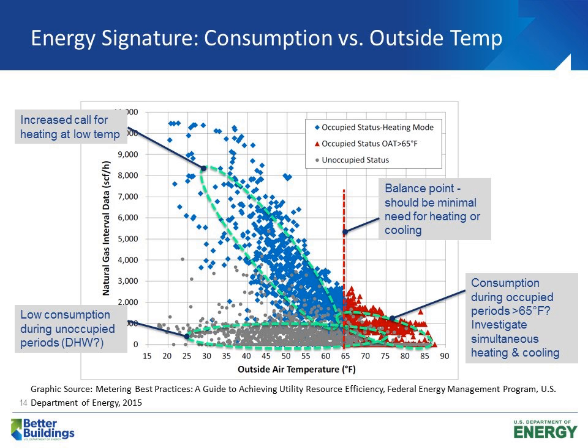In this case, unoccupied is shown as gray, and it's nice that unoccupied energy use is low. You can see your balance point and the slope of this line. Some do regressions, so you can compare your heating slope to benchmarks. So an energy signature, whether on the gas side, electric side, or total BTU side, is a nice way to see if you have simultaneous heating and cooling, or if you're doing reheat when you didn't want to be.